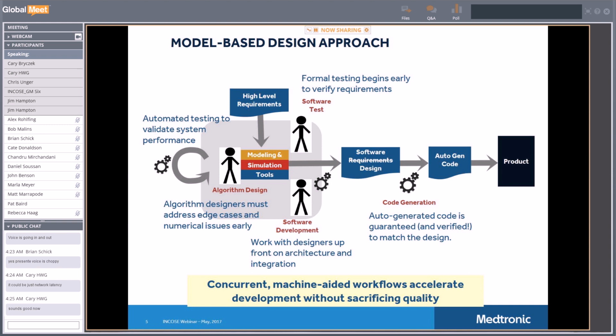Now, at the working level, if people ask me, can you show me something in the design? I would just open up the tool and show them on my computer where this is done in the design. Of course, in a regulated industry, you have to have design control documentation and so forth, something to put into doc control that documents your design and shows all the traceability in basically paper format. Fortunately, that can be done automatically using the tools provided with these model-based design tools, to automatically generate your design documentation for compliance purposes.